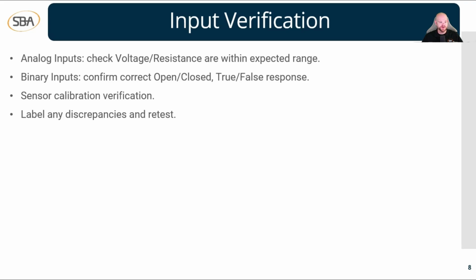On the other side of our inputs here, on binary inputs, we're just going to confirm the contacts are working as they should. So if it's normally open, normally closed, versus when it's energized, make sure that contact's responding how it's supposed to. And then true-false responses as well. Again, binary is just a two-state point, so it's just going to be either on or off, true or false. They're kind of interchangeable here. So that's when we're checking those, just making sure we're getting a status or something coming on and off. Should be good there. Third point here with input verification is sensor calibration verification.